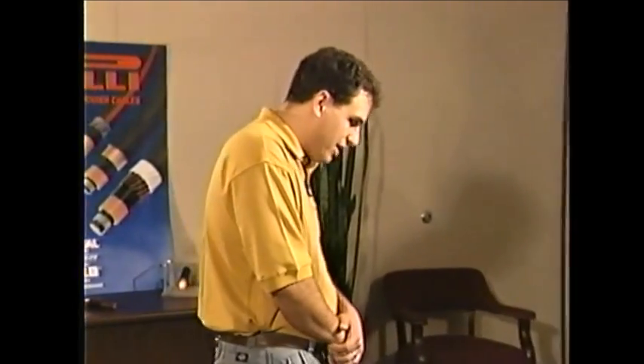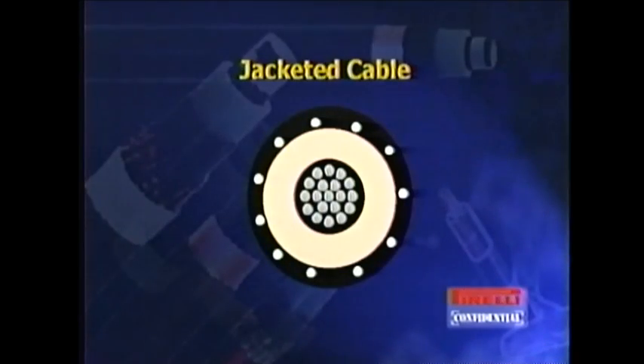However, we've gone through all the trouble of making this beautiful, symmetrical, nicely shaped power cable. We want to have some means of protecting it. If we put this in a direct buried application or into a conduit where you're subjecting the cable to mechanical stresses, you could cause damage to the cable, possibly nicking the insulation, maybe distorting it, or doing something that's going to damage this beautiful cable that you've built up. So to prevent this situation, what we normally do, and we've seen this more in recent years, is have some type of a jacket over the cable.